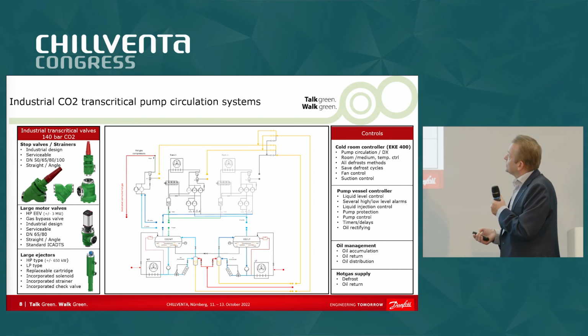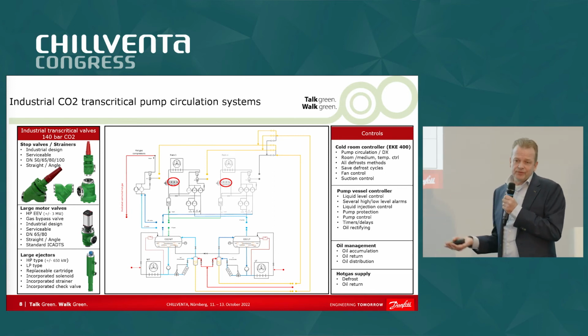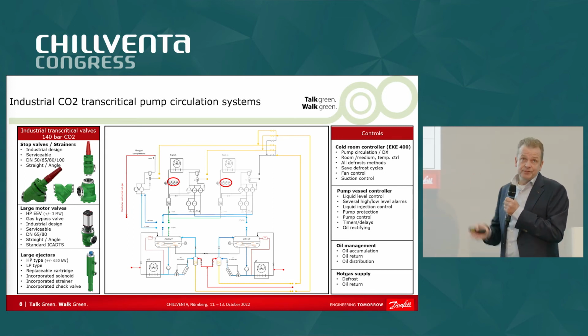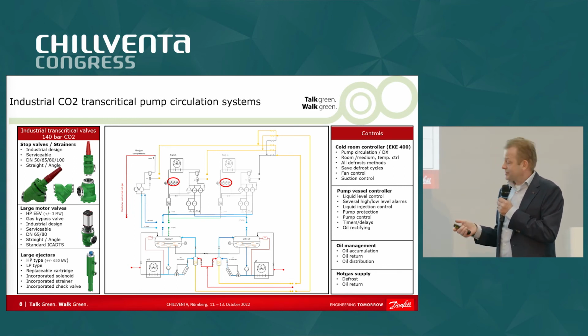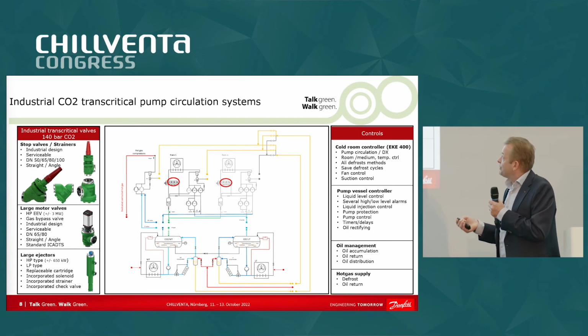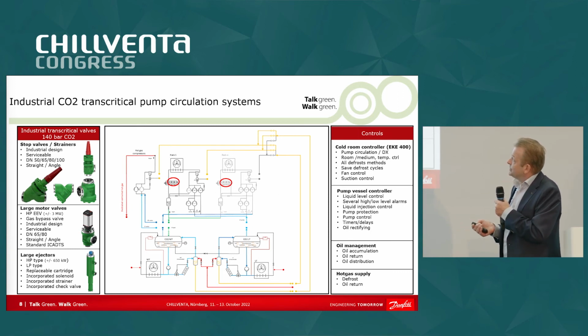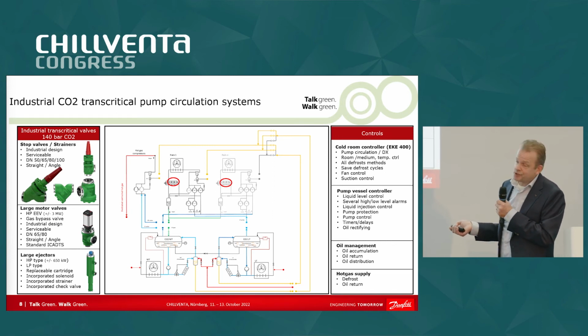Also, I put in some ejectors here. So what is an ejector? An ejector is basically an expansion valve, but it harvests the expansion energy. So it can suck, in this case, some gas from any part of the system to support the medium temperature compressors. So the expansion valves are here, and we get an automatic suction flow through the ejectors to support the medium temperature compressor. So you get a better efficiency. COP is going to be higher.